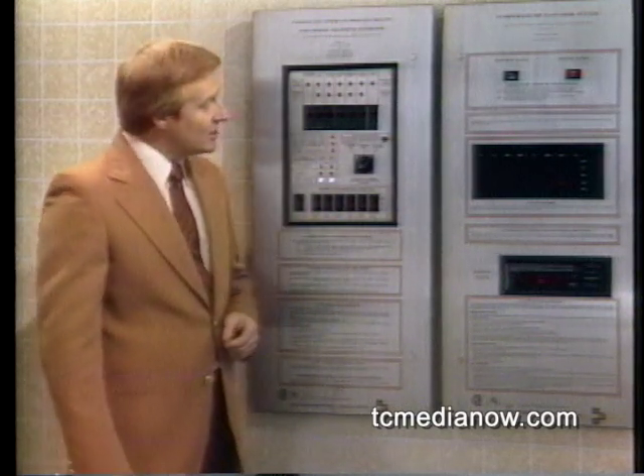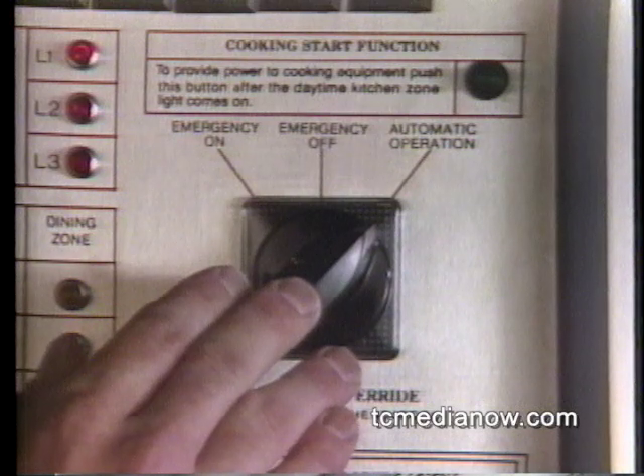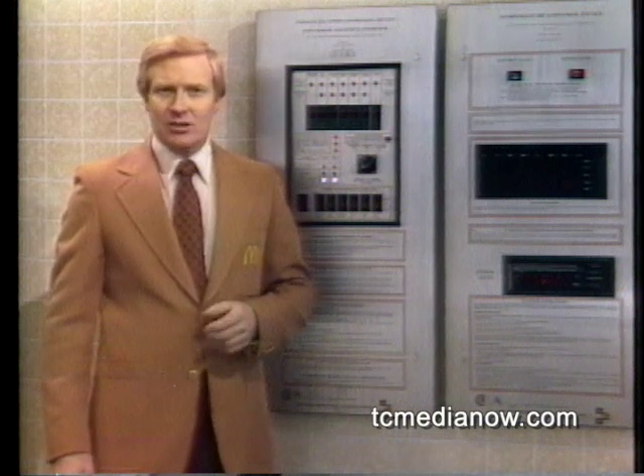The Energy Interlock system is designed for fully automatic operation. The store manager simply sets the system clock to the desired operating times. The Energy Interlock system then performs all necessary operations with practically no further attention. The manager may override the automatic system at any time using the switch labeled Emergency On or Off. This switch must never be used except in a true emergency, such as a complete system malfunction, since improperly overriding the automatic system can cause total loss of accumulated energy savings.